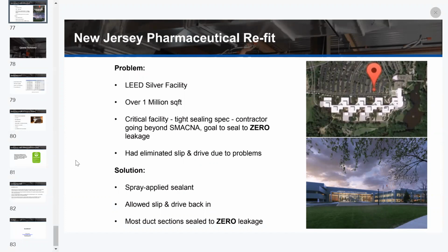New Jersey pharmaceutical refit. The building was over 1 million square feet, almost a quarter-mile long, 3 stories tall. Critical facility as a pharmaceutical. They had a tight sealing spec, but the contractor was pushing for as close to 0 duct leakage as possible. And the contractor had actually eliminated slip and drive construction from their jobs prior to this due to challenges of sealing those. They would test for leakage multiple times, go fix, find out where the leaks were until the system passed. Spray seal was used on this one as well.